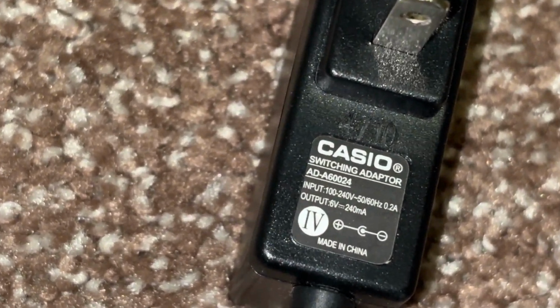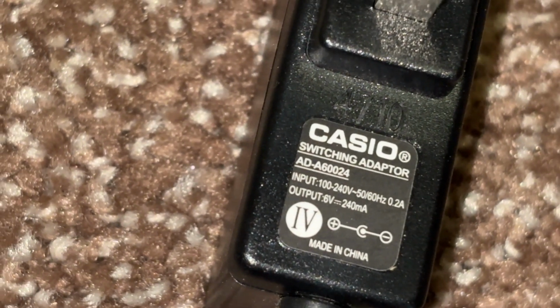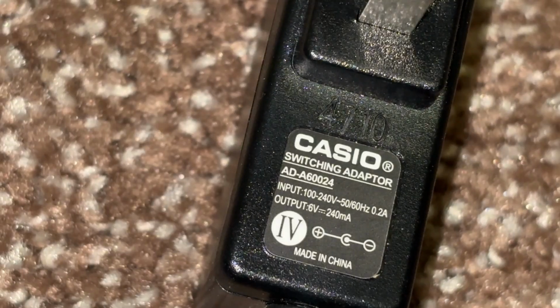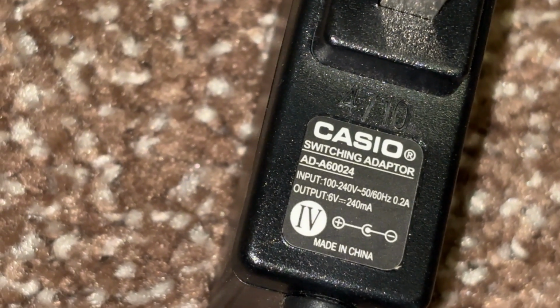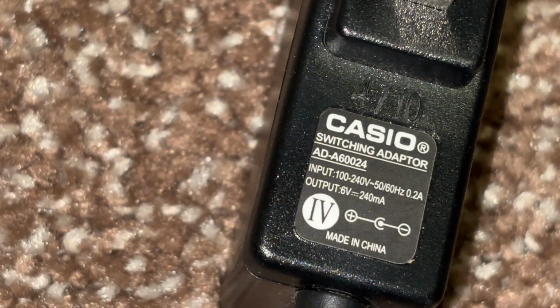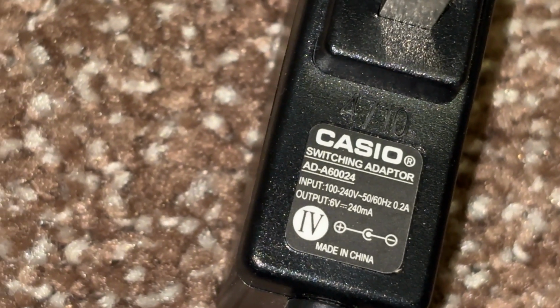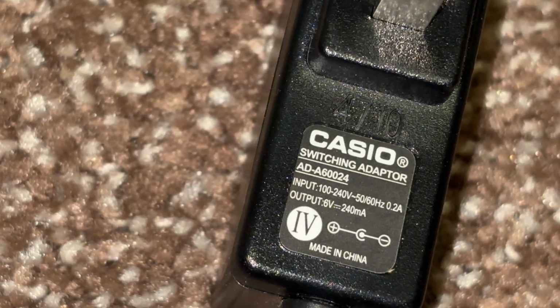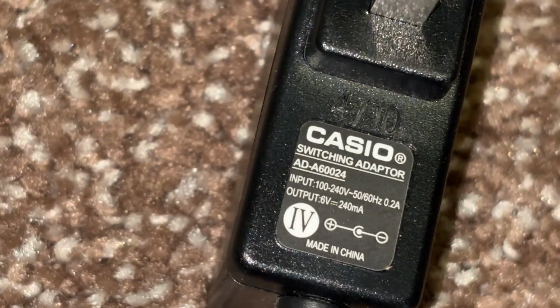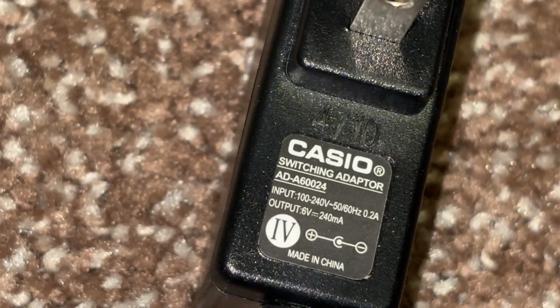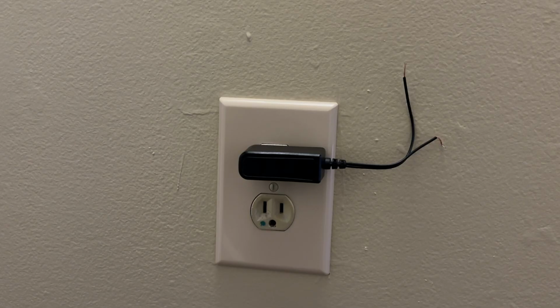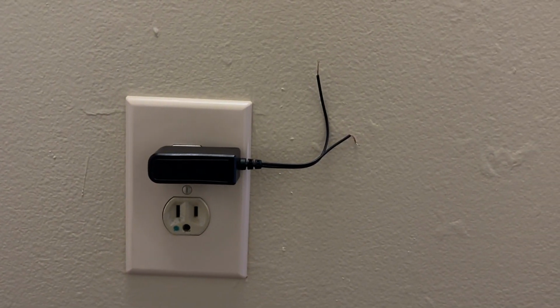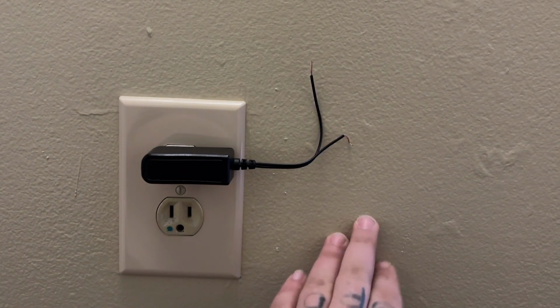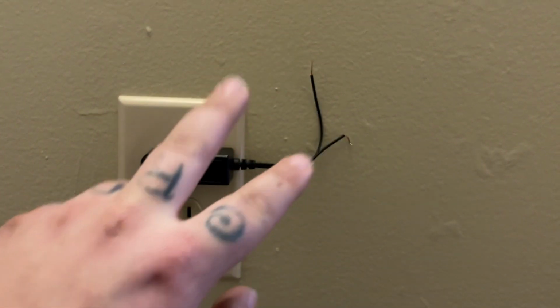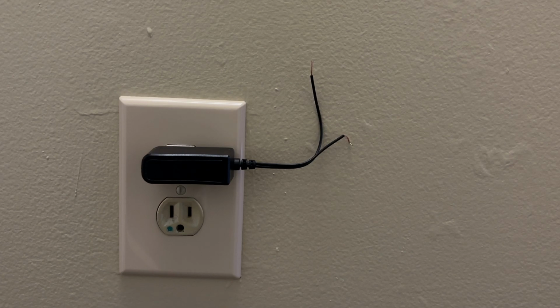If you notice the difference in the symbols there, the one after 240 volt is a wavy symbol, which indicates it's alternating current, AC. The output of 6 volt is the line with the dots, indicating it is direct current, DC. So not only does this transform the power into a smaller voltage, it also switches it from AC to DC. If you have these style plugs, they will usually be located in your HVAC closet, mechanical closet, or similar, and they would have a plug, and then usually a blank, and behind that blank is where these wires go in and your wire nuts attach to send it on to your switches and your strobe.